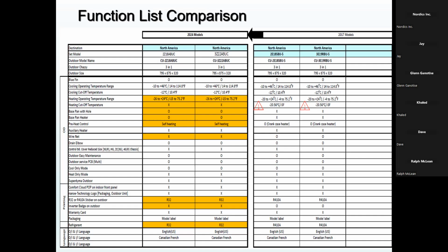Having said that, good down to minus 26 does not mean that you're going to get 100% capacity. No. As you all know, being in the trade for many years, as the temperature drops, the capacity drops. So that's the difference between the old and the new multi-zone. No cutoff, and it operates down to minus 26. R-32 refrigerant. Obviously, the old one did not have a base pan heater. The new one does have. So that's a pretty good North American system that can work from coast to coast to coast with no issues whatsoever.